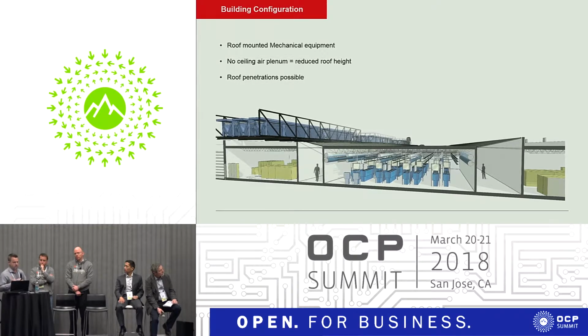One of the big things here with the building configuration is because we have no open loop water systems, we have no cooling towers, et cetera, we don't have any large sources of water to worry about. We do have a process cooling loop that is a closed loop system. The heat rejection equipment for the immersion cooled solution is completely dry coolers. No evaporative pre-cooling media is required. So one of the things that does allow is if an owner wanted to even further consolidate the space requirement, you can put the coolers up on the roof. You don't have the leak concerns that you have with a water-cooled plant.